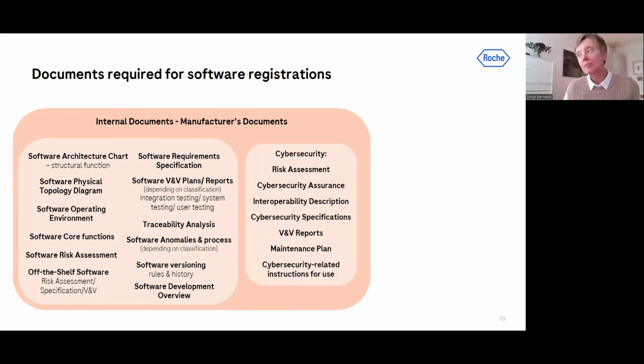In addition, you need to provide cybersecurity documents, and China is focusing more and more on cybersecurity. So those documents are very similar to what you would provide in the US. However, there are slight differences regarding the composition or the structure of those documents. And here again, make sure that you consider the latest cybersecurity guidance for medical devices in China to make sure you have all the contents that are required, but also the formats and the structure that the reviewer will expect here. And maybe a little bit different from the US submissions, you also need to provide those parts of your instructions for use that are cybersecurity related.